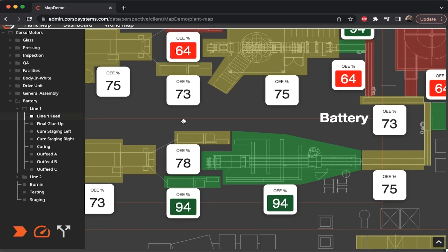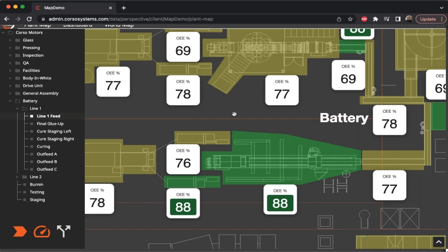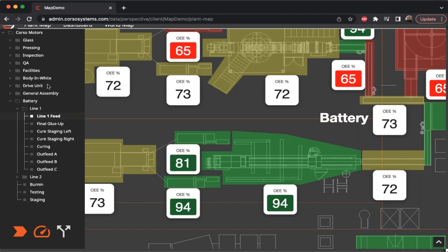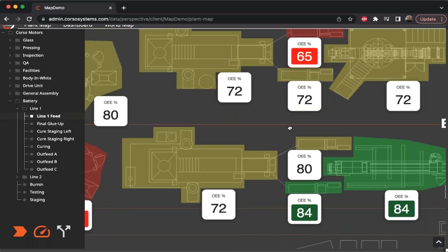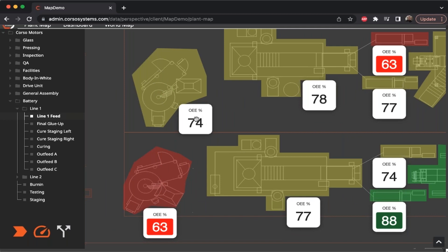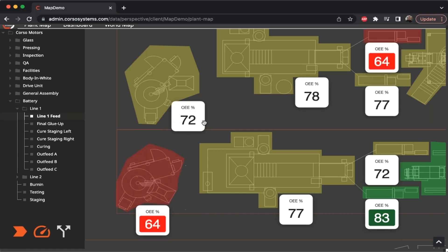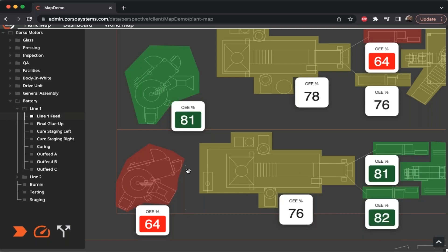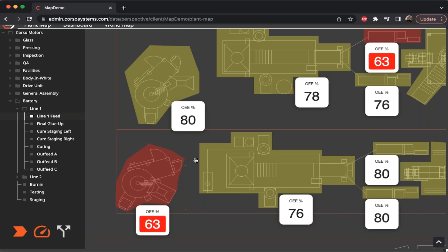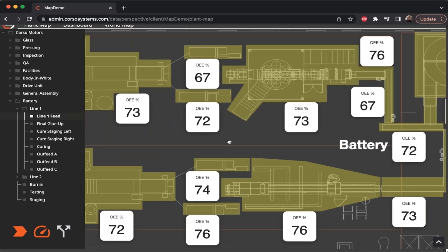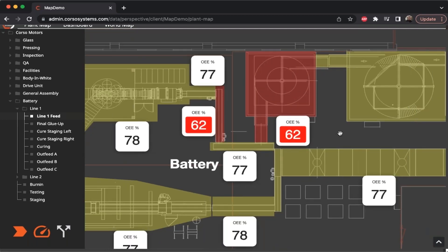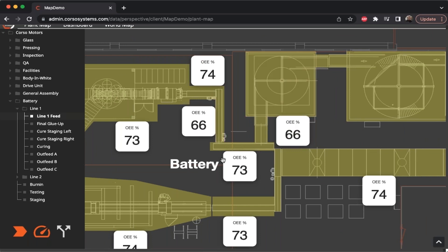We can also save these views to show on screens on the plant floor, or pull up different views for pieces of equipment outside of the ISA-95 hierarchy. On the map, we have an OEE dashboard icon that could include things like sparklines, tabular data, and different labels. This ties into all of the tags in Ignition. In this project, we have a UDT developed for all of the equipment and components we want to display on the map, so we can pull those tags in and automatically populate devices on the map. In the PLCs, we also have add-on instructions to map all of the tags from PLC and IO devices into Ignition, so doing some work up front to standardize all of that simplifies getting things onto the map.